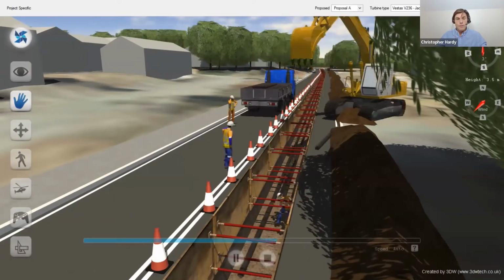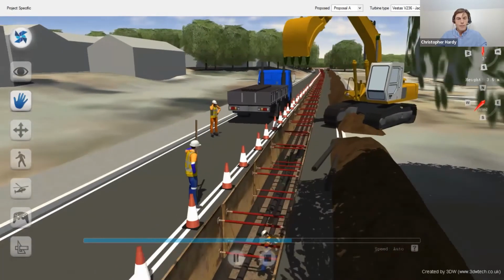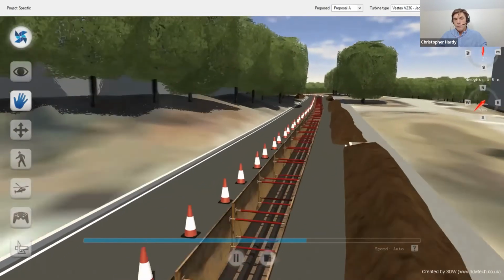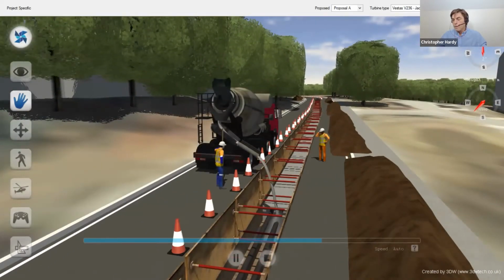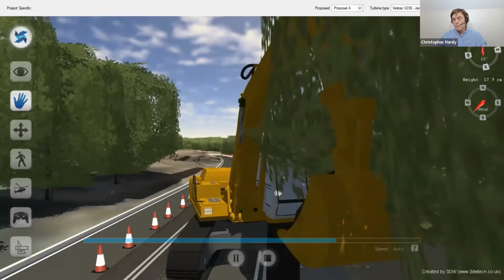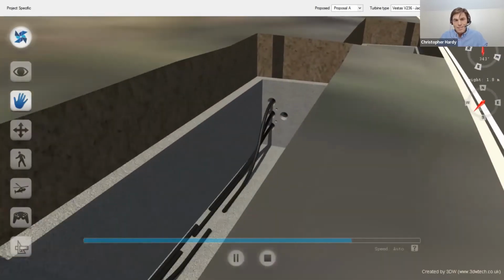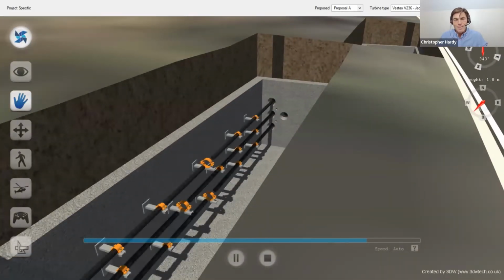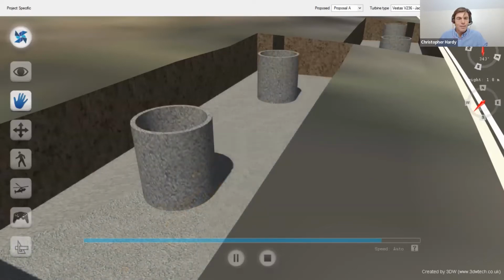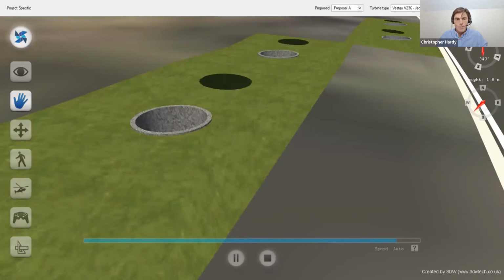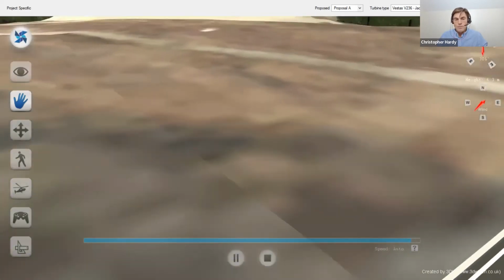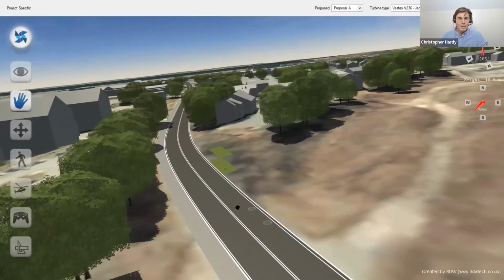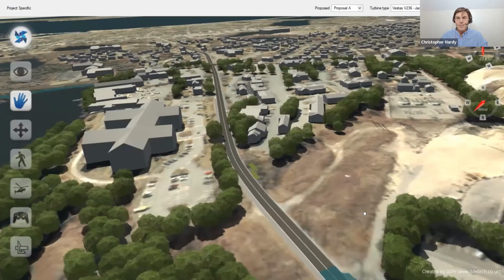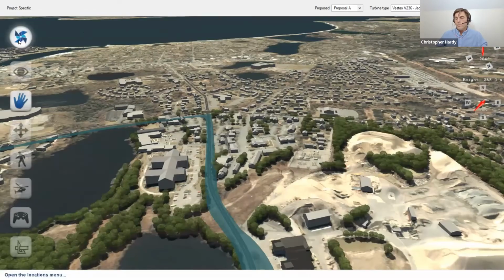After the trench is dug, the backfill is filled in, the cable conduit is laid, ducts are laid. Segments of plastic pipe are what the ducts consist of. They're encased in concrete. The backfill is filled and then covered and repaved. Here the cables are coming into the transition vault, or splice vault rather, which are every third to half mile. That was a quick open trench installation sequence. Each vault is approximately 30 feet long, 8 feet wide, and it's dug at a depth of about 13 feet.